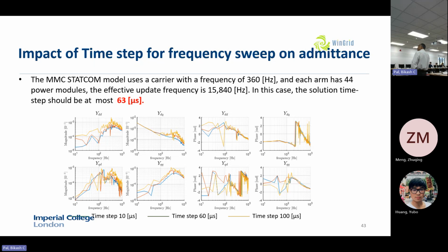So we have a STATCOM MMC with a carrier frequency of 360 Hz, and if each arm has about 44 power modules to build the voltage, the effective update frequency has to be 15 kilohertz. That means for every 63 microseconds we must finish our computations. It should be at most 63 microseconds—the sampling cannot be slow.